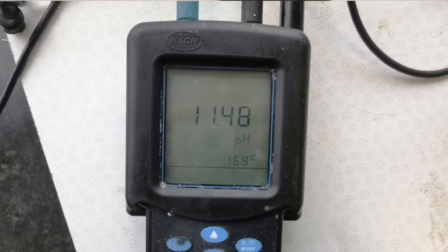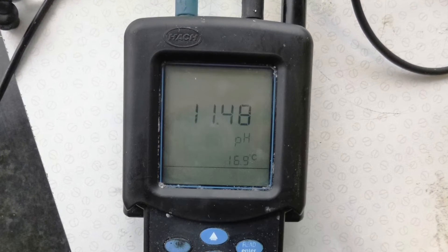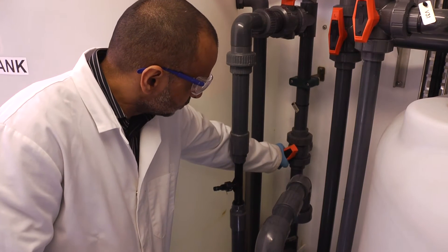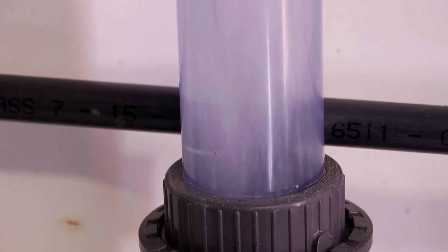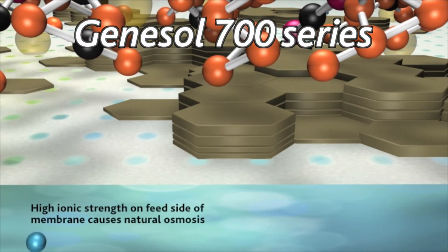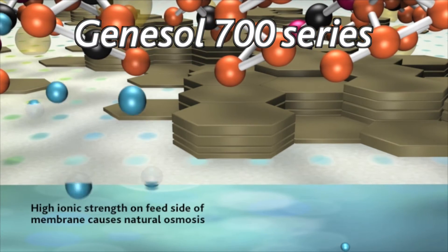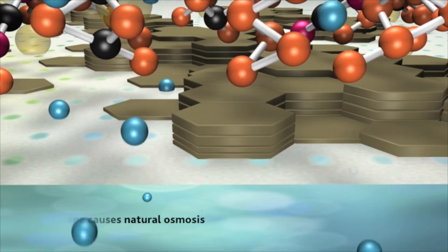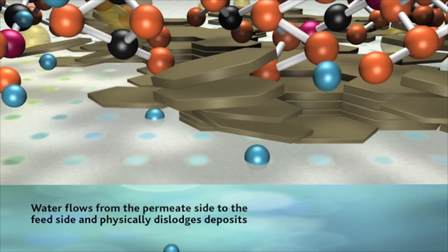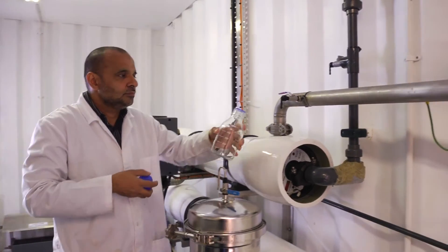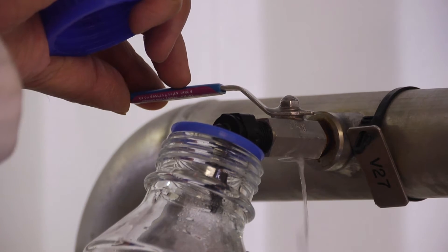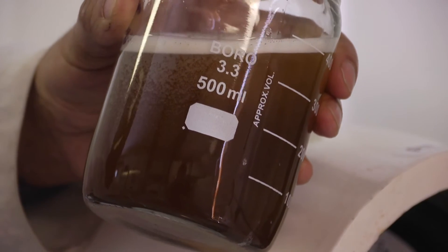Adjust pH and temperature to comply with the manufacturer's guidelines. Recirculate the cleaning solution for 30 minutes. Soak the membranes for 30 minutes to determine the extent of organic fouling. During soaking, normal osmosis causes permeate flow back through the membrane, loosening deposits. If the solution becomes discoloured, discard and make up a new batch. Repeat 2 or 3 times depending on the extent of the fouling.